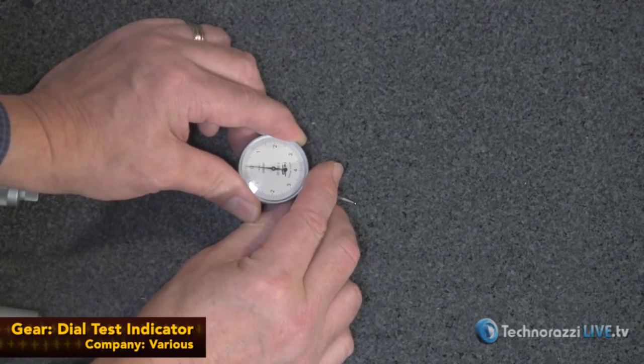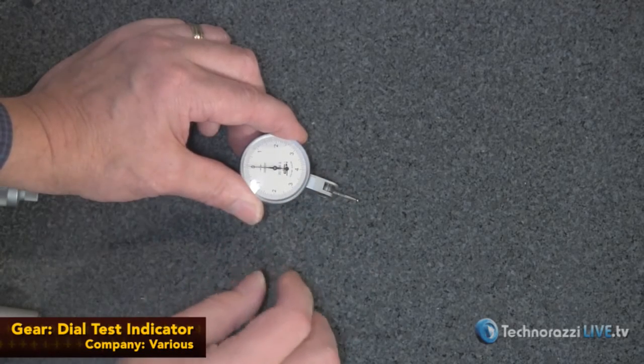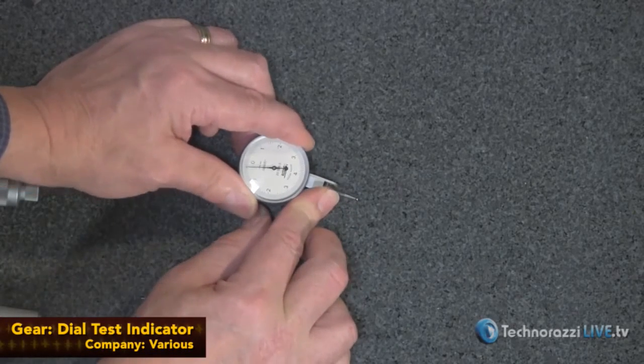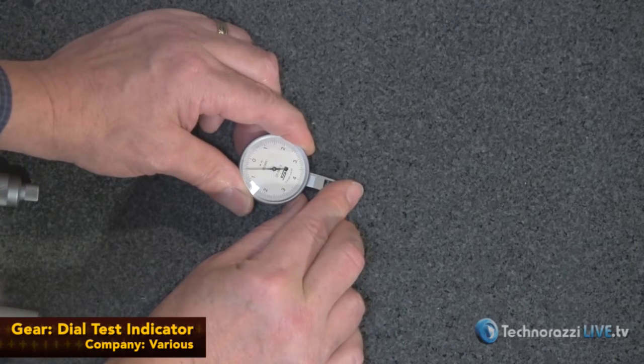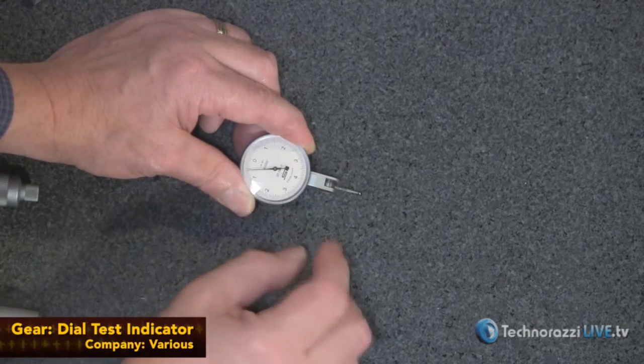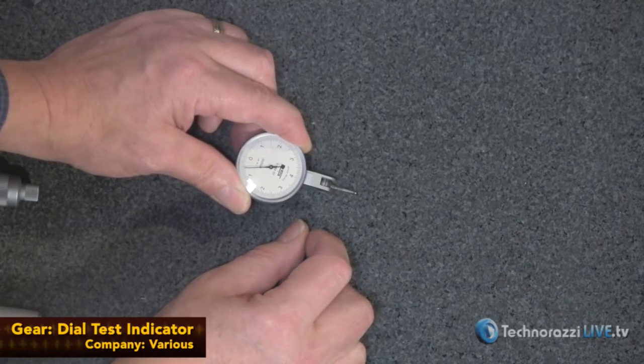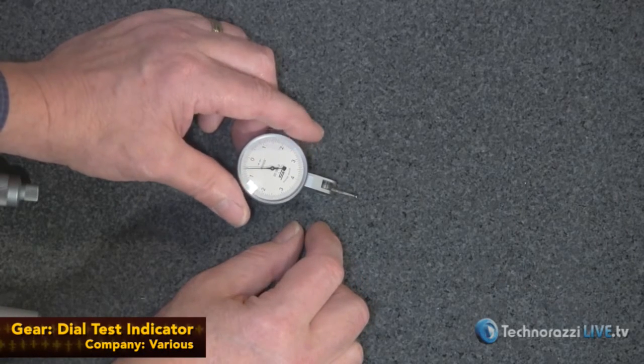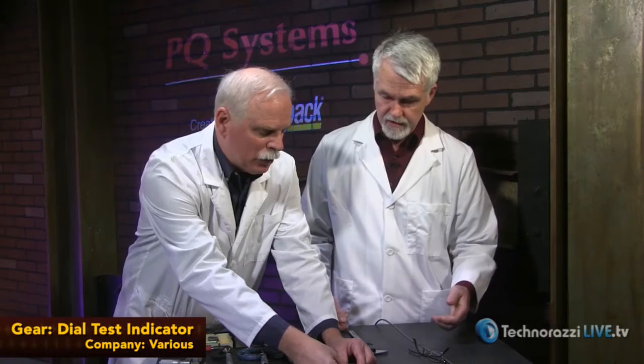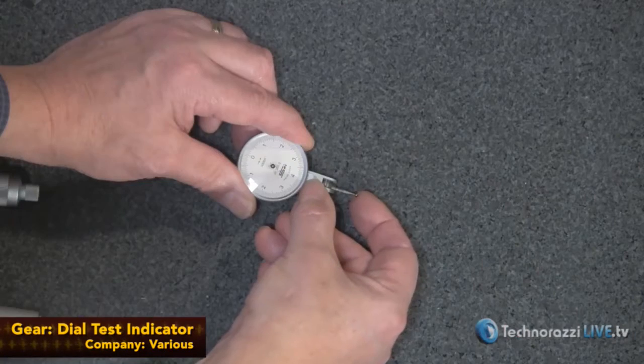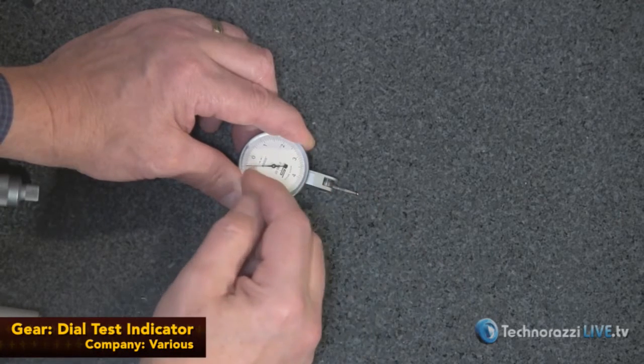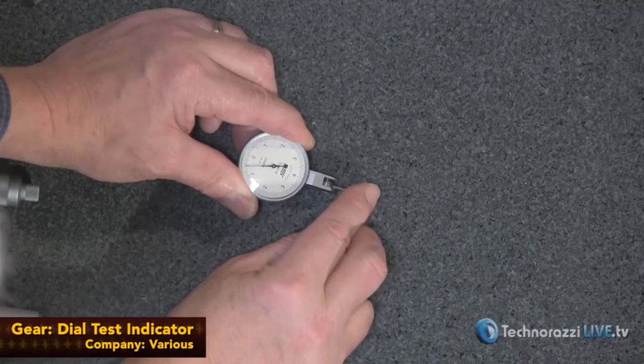Number one, you can't tell if the needle would have kept going. You always want it to be under a load so that when you hit 0, you can see if it goes below. And it's spring actuated, so it needs to be under tension. So again, you're also kind of feeling or looking for smoothness. Smooth movement. These will really tend to not repeat when they go bad. You won't get the same final 0 point. That's a good check. We check them both from above and below.